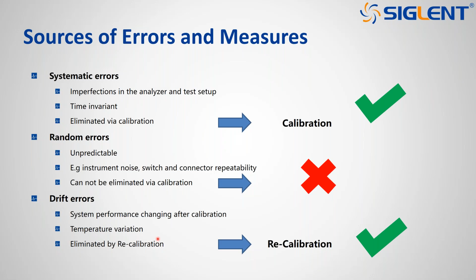Drift errors means, especially now in summertime here in our office, if I would do a calibration in the morning where we have 18 degrees with open windows, and now in the evening we have 25 degrees, there will be a temperature drift. And if I did the calibration in the morning, honestly, I should do it again to compensate everything. This can also be fixed and eliminated, but this is something you have to consider and think about, depending, of course, on how accurately you want to measure.